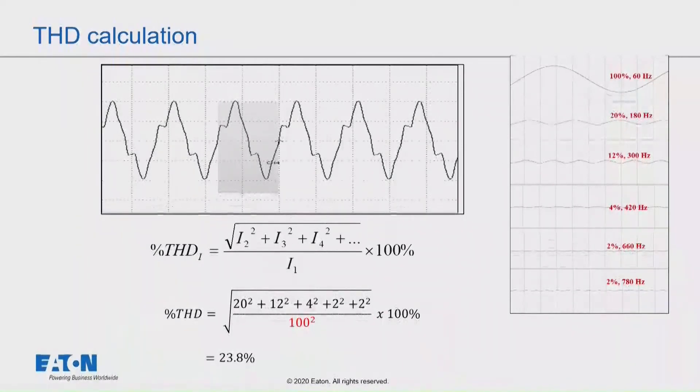In this case, since the fundamental is 100%, let's just use 100 amps as the number. And so we would have 20 amps of third harmonic, 12 amps of fifth, and so forth. As you can see, the higher order harmonics really don't become a big number when you square them. So the lower order harmonics are significant. And we end up with a number that's about 24% distortion.